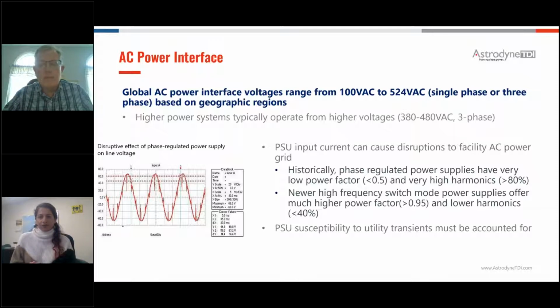So you'll generally see these supplies operate from a higher voltage line, something like a 380 to 480 volt three-phase line. We need to be cautious in terms of how we specify the power supply, because the power supply can actually cause disruptions on the power line that could cause problems in other equipment that cohabitates with your system. For instance, if you look back long enough, historically phase-regulated thyristors were used to control output power, and they can really take a chunk out of the AC line as they operate. You can see on the left a screenshot of an AC line in an actual application where the AC line was very badly corrupted by a phase-regulated SCR type of supply operating. So you need to be careful that you don't want to be the one responsible for causing other equipment to malfunction. And likewise, if there's other equipment like that in your facility, welding equipment comes to mind, you need to make sure that your system and your power supply is not corrupted by an AC line like that.